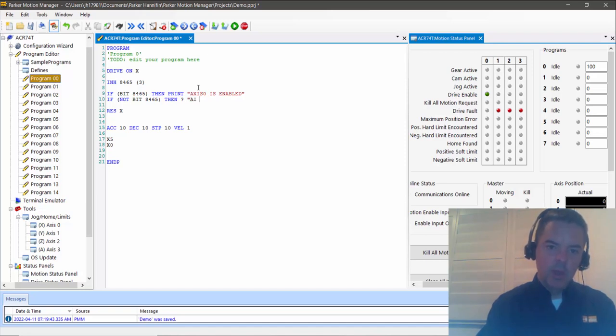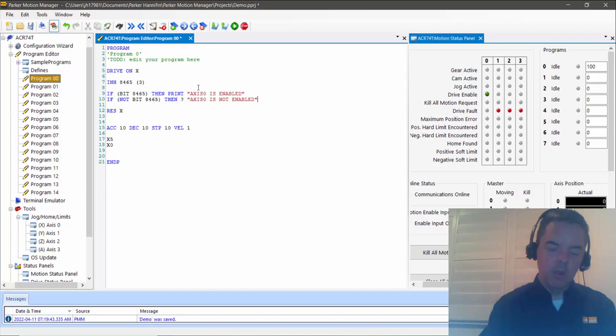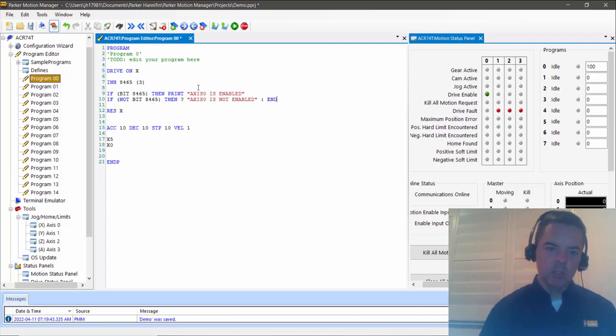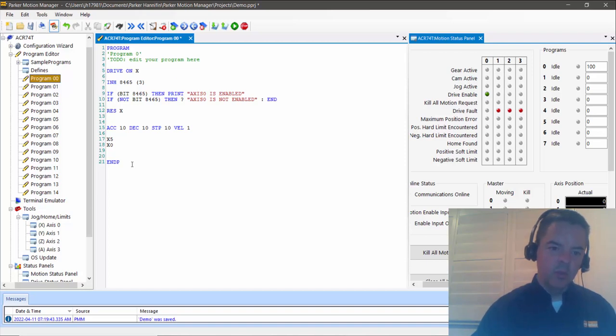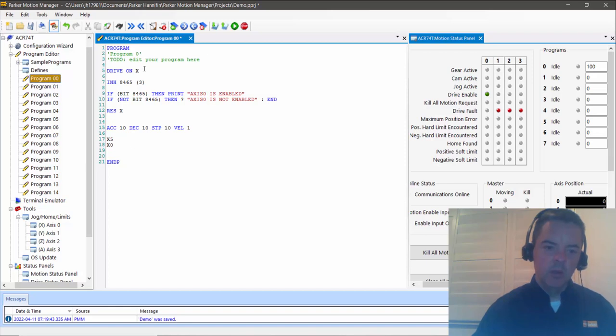Axis zero is not enabled. And then if the motor is not energized, obviously we would not want to view the motion, so then we would want to end the program. So END just stops the program from there, not to be confused with ENDP at the bottom of the program, which defines the end of the entire program.